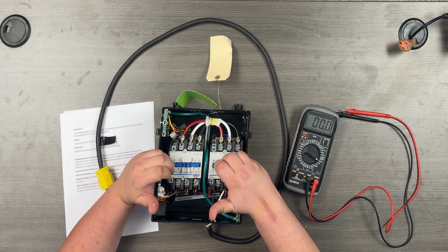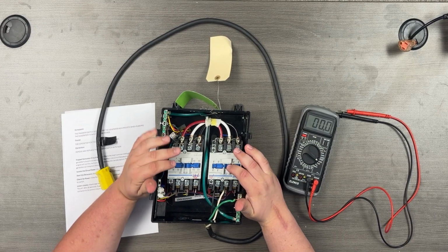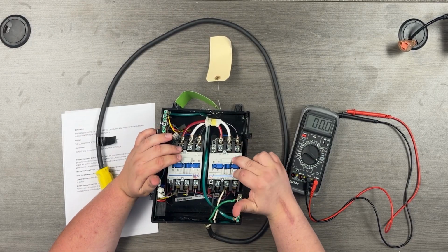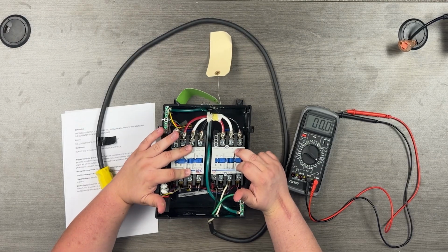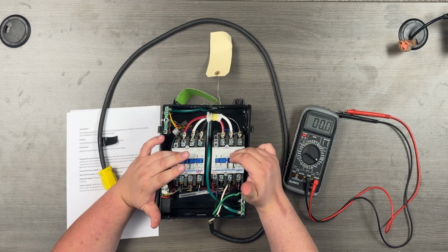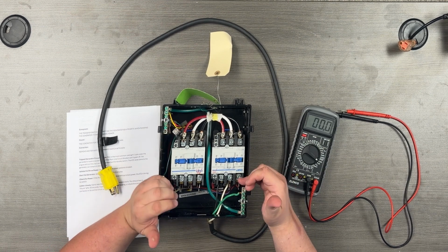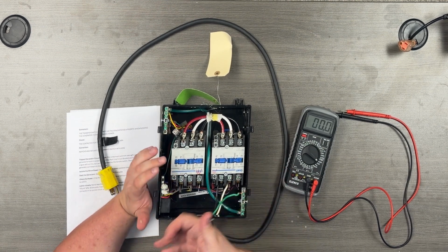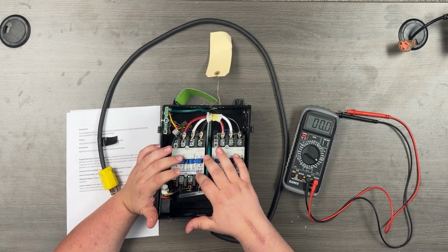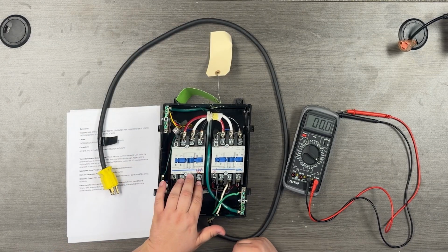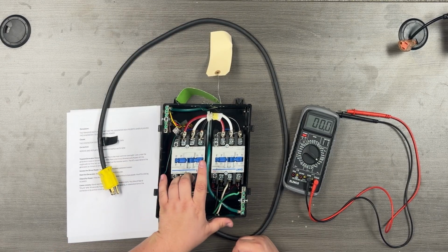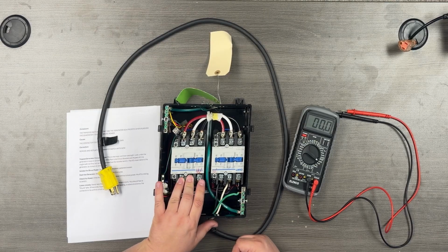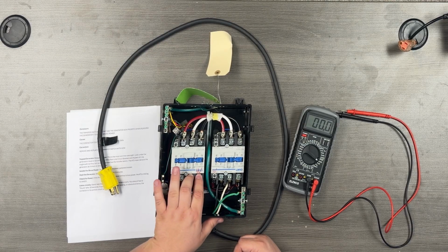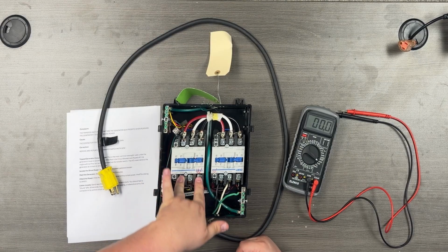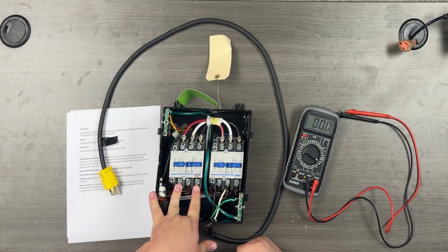So we've got our two different contactors in here. We've got our shore power side and we've got our generator side. We always want to make sure when we're testing, whichever one that we're testing, so for this customer complaint, we would be looking at the generator side. We want to test on this side, go from hot to neutral. Do we see 120 volts? If we're dealing with the 50 amp, we want to test both legs, and then you want to test across so that you see 240 volts when you're testing across this way.